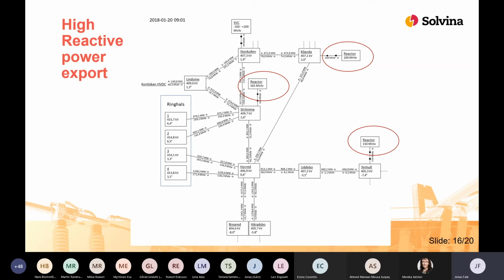Here we can see a case with high reactive power production from Ringhals. The reactive power production is inside this range of what the units are obligated to be able to produce. So it shouldn't be a problem with the reactive power production. However, this situation indicates that there might be instances where the resources in the area could be used more efficiently. This is since we see that Ringhals is producing a lot of reactive power, and we have all of the reactive resources connected, all of the shunt reactors, and also this SVC in Stenkullen is absorbing reactive power.